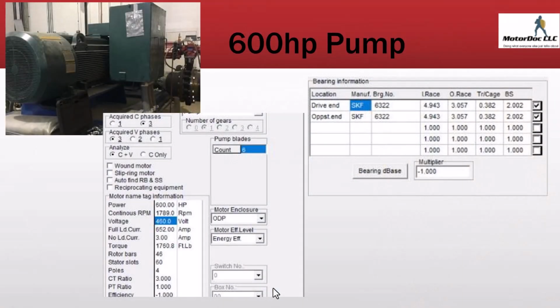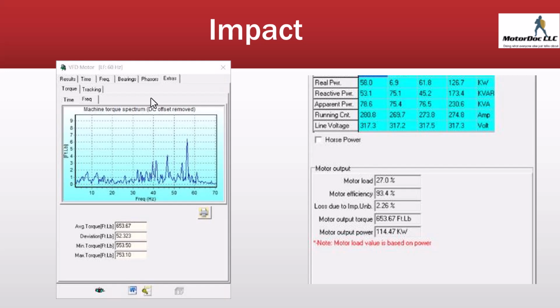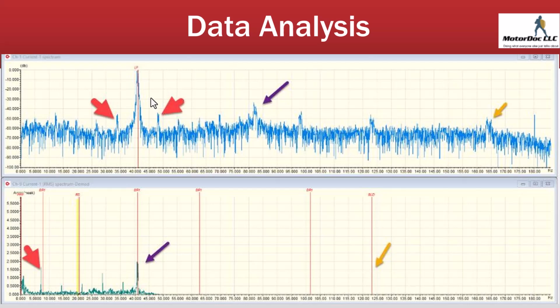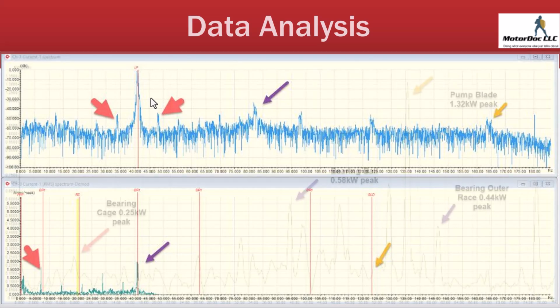So let's take a look at a 600 horsepower motor and pump, this 460 on a VFD. They have some very definite alignment issues. I don't know if I have a picture of how awful that is, but they used undersized shims. So we ended up with all kinds of problems, including it taking out the bearings. So overall, bearing issues and some other stuff. These are the bearings again.